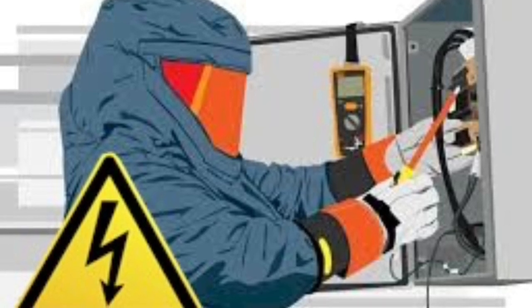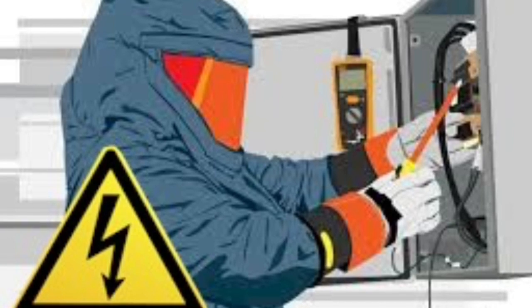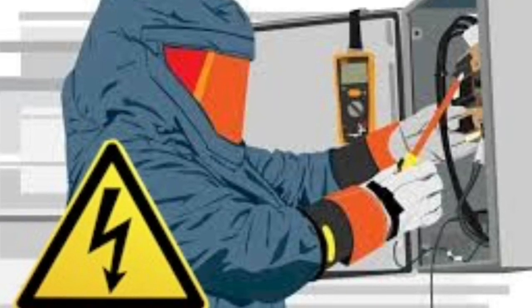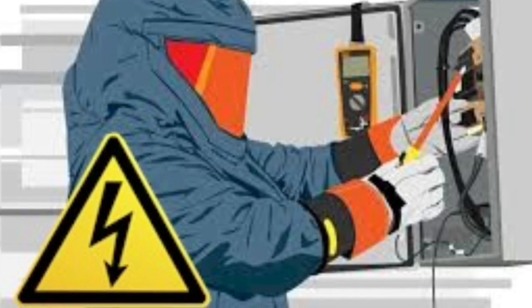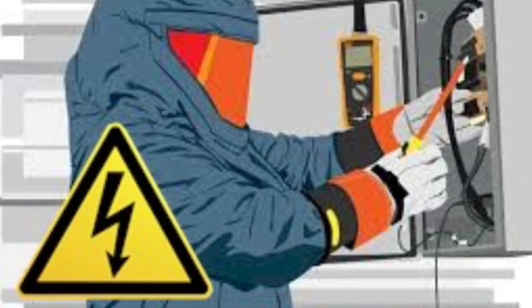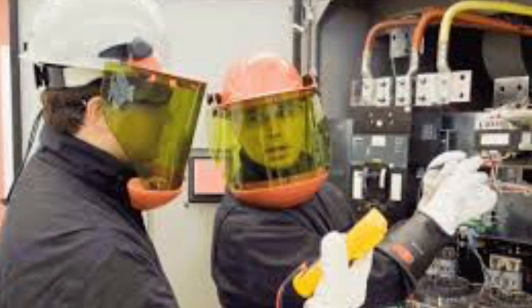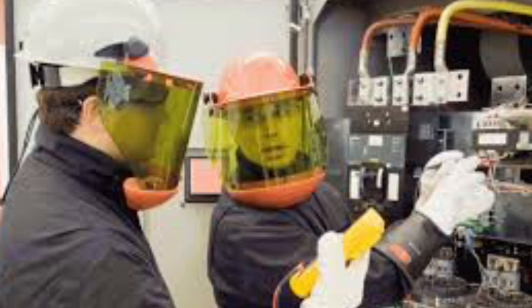The phrase "has demonstrated skills" requires that the person must actually demonstrate the ability to perform the task. It may be necessary to demonstrate the ability to perform the task while using appropriate PPE to ensure that the restricted lighting and field of view of the arc flash suit hood or the dexterity limitations of voltage-rated gloves with leather protectors do not hinder the employee. Part of this training is about learning how to select and use the personal and other protective equipment required to perform the task safely. Training may be completed in incremental steps.